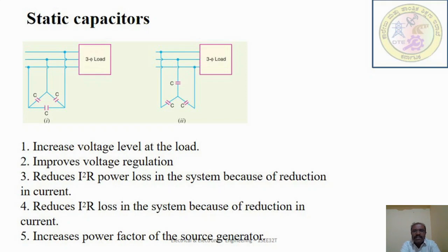This method is widely used in industries and substations, as there are no moving parts in this. It requires less maintenance. However, repair of capacitor is not economical once they are damaged. You can see the advantages. They have low losses. They require little maintenance because they have no rotating parts. They can be easily installed as they are light and require no foundation. They can work under ordinary atmospheric condition.